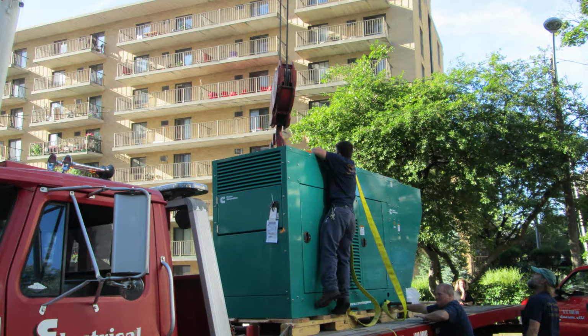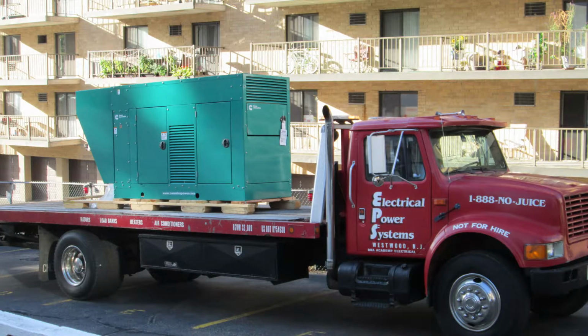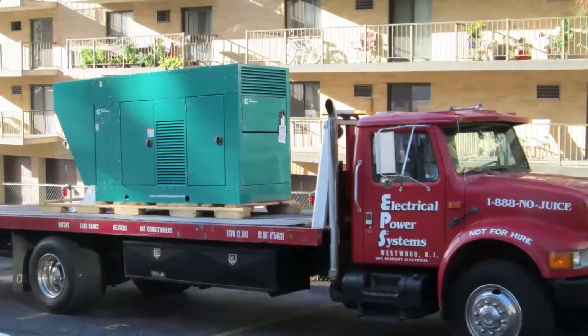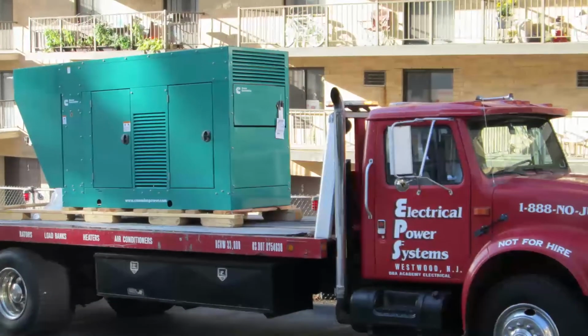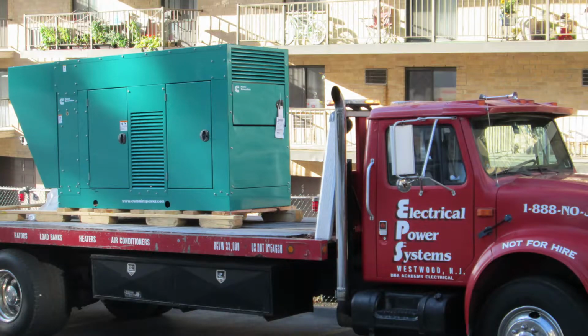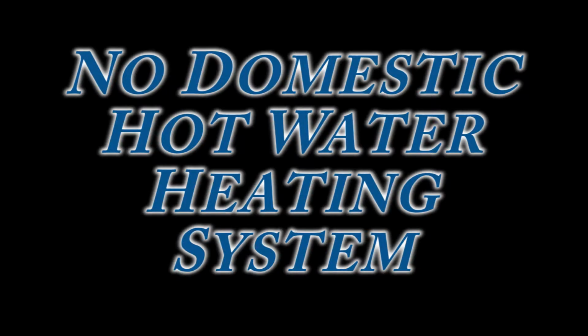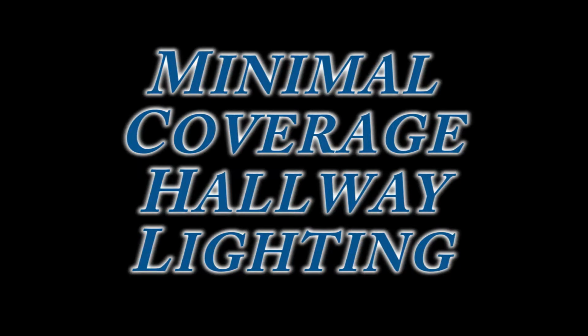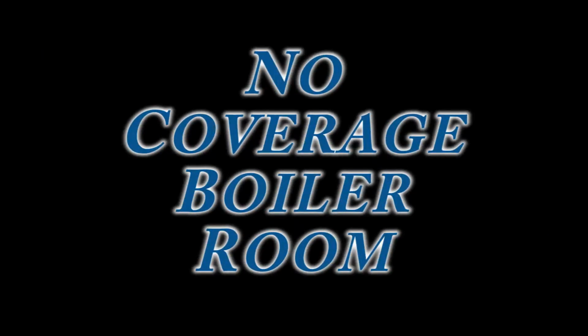They had 2 small 30 kW gensets there now, both of which were older Onan gensets, and we were going to replace this with one new 100 kW natural gas genset to pick up the existing loads and the additional stuff that they wanted in the building. Currently, they had no domestic hot water system on the genset, so they had no domestic hot water, and the lighting in the hallways was minimal at best. The boiler room wasn't picked up.